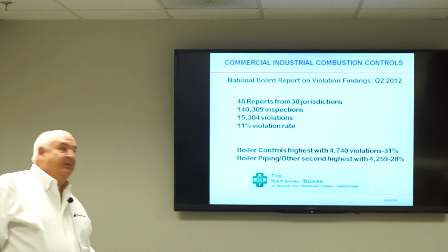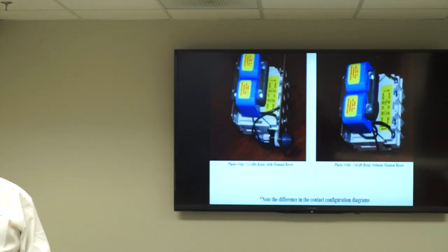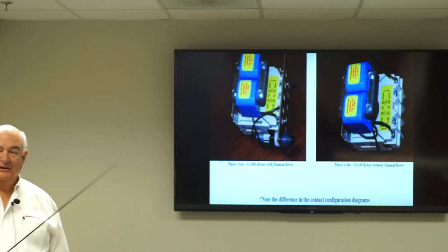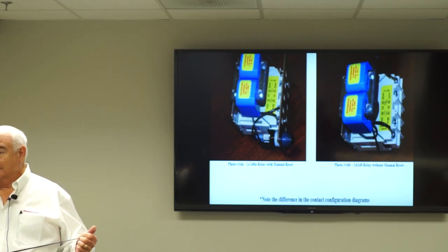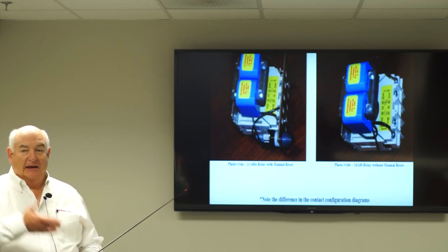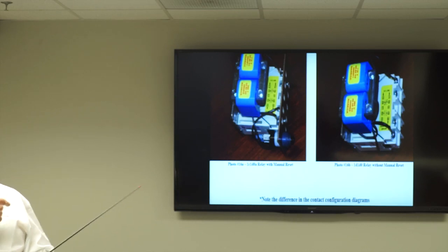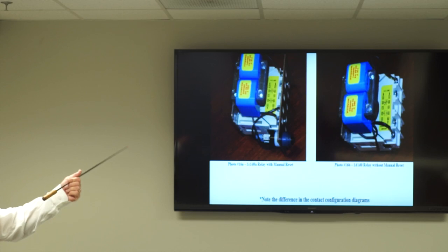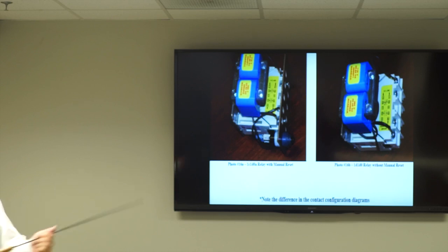The result was that some people got hurt. The guy was a little cherry red himself, but didn't have to be hospitalized. Interestingly, these boilers have to be inspected by insurance companies because they carry liability. An insurance inspector had looked at this boiler two and a half weeks prior to the incident and checked off that it was in good operating condition — when it clearly was not, since these two safeties were inoperative and should have been detected.